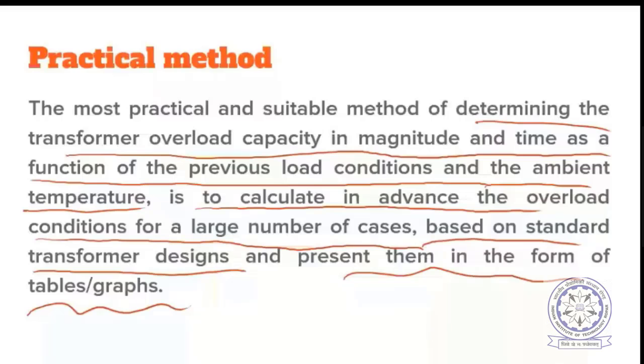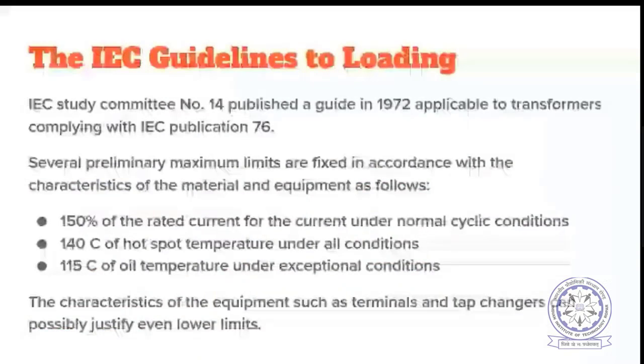So what are the IEC guidelines for loading? The IEC study committee number 14 published a guide in 1972 applicable to transformers complying with IEC publication 76. Several preliminary maximum limits are fixed in accordance with the characteristics of the material and equipment. As per the load, it is 150% of the rated current under normal cyclic conditions. Under recurrent load conditions, you can go up to 150% of the rated current. This is the maximum limit proposed.